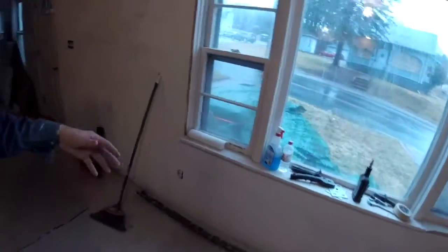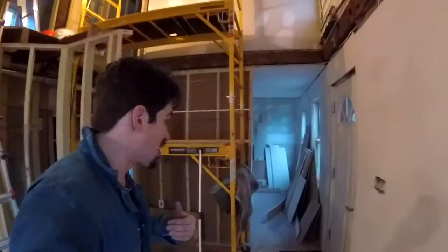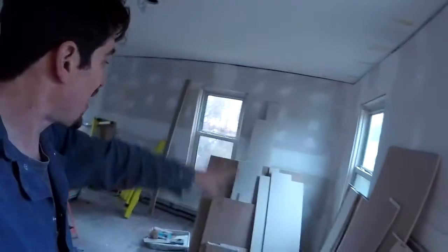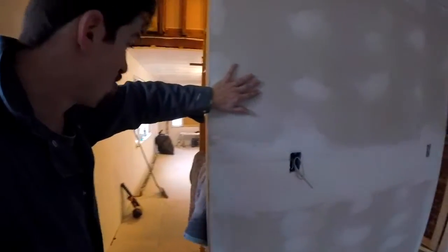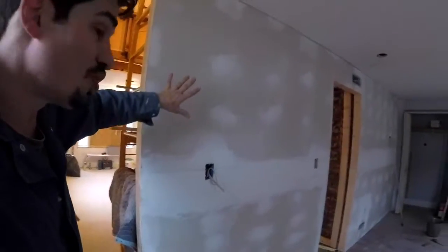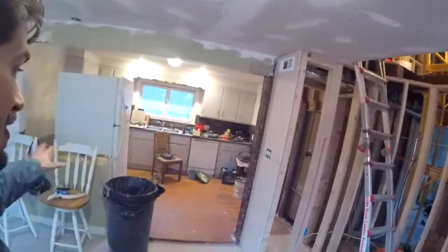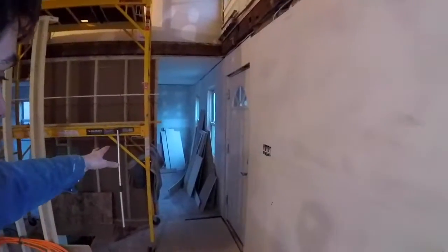We have these radiators, and being two zones means we have two thermostats and two circulators. It's going to circulate on the first floor as one zone, and we're going to have a thermostat here in the living room. This is on the northern side of the house, so it's going to be the coldest room — that's where the thermostat is. The air will warm up this room and once it reaches temperature, it turns off. But the registers run throughout the house including the hallway, kitchen, and bathroom, so it could be scalding hot in those areas and not registering on the thermostat. Plus with this big wide open space, we have this massive heat sink drawing all the air up.